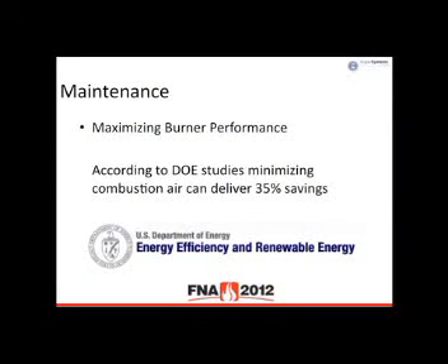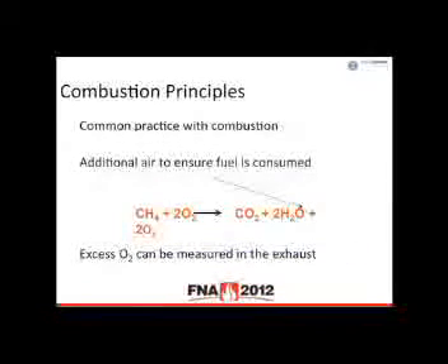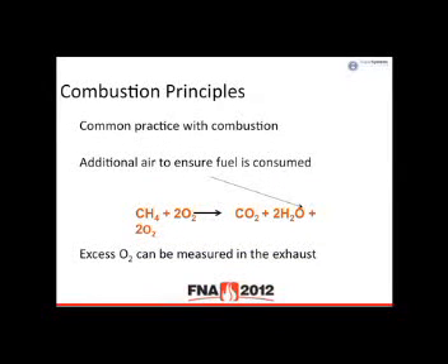Damien, who was on earlier, touched on this as well. Another opportunity for capturing information. I use this Department of Energy slide: minimizing combustion air can deliver 35% savings. So what you do is you measure the oxygen in the exhaust gas of your burners. When you're measuring the oxygen in the exhaust gas, you have an opportunity to create higher levels of productivity for that furnace. You're basically increasing the heating capacity.